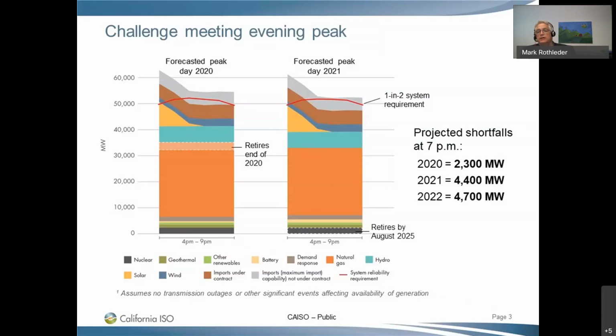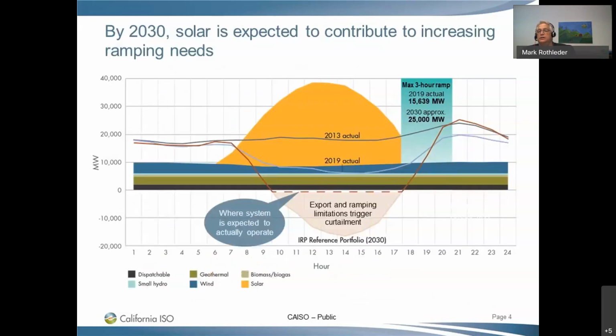The next challenge is the continued increase in solar resources. We're seeing our net load continuing to decrease, and in fact we're now at points where, on a 50,000 megawatt peak system, net loads are approaching just under 4,000, around 3,500 megawatts. We're going to get to the point where net load will actually drop below zero. The consequence is that as evening comes and solar production goes down, we're seeing increasing need for ramping capability in that evening period.